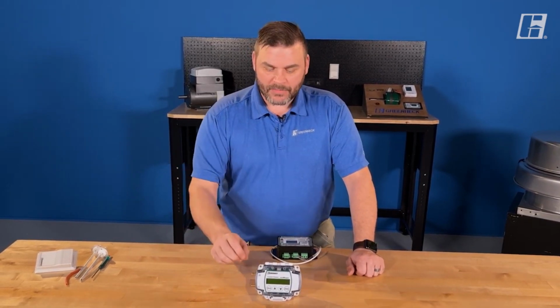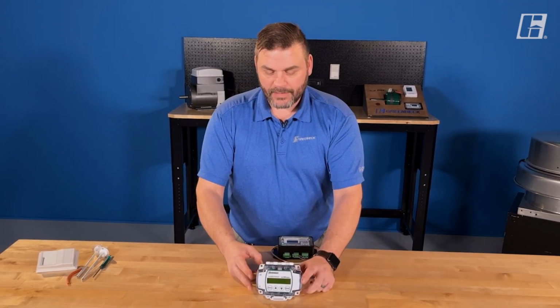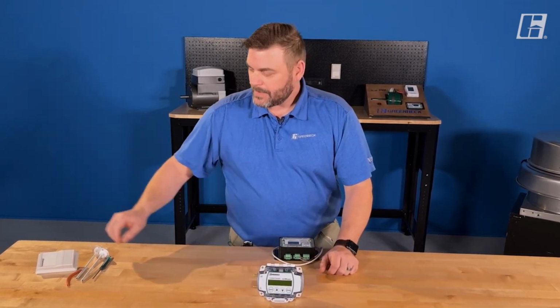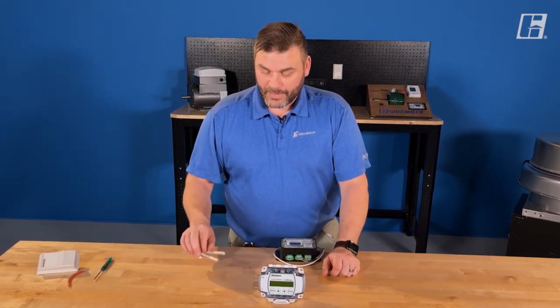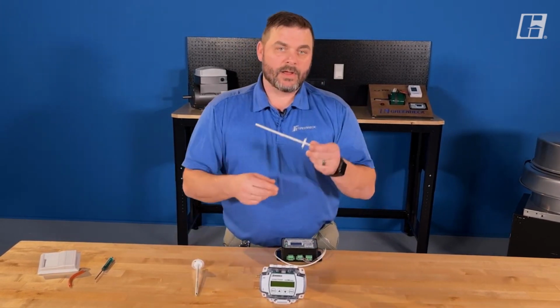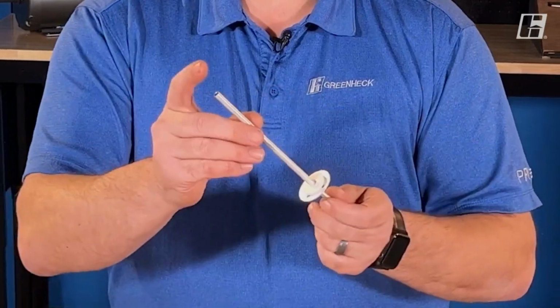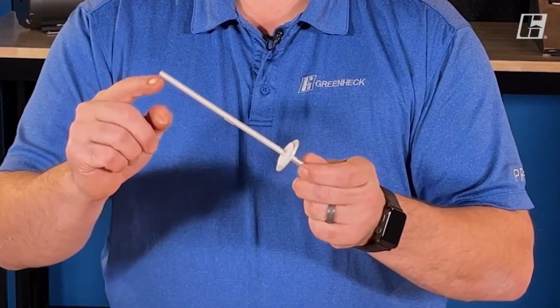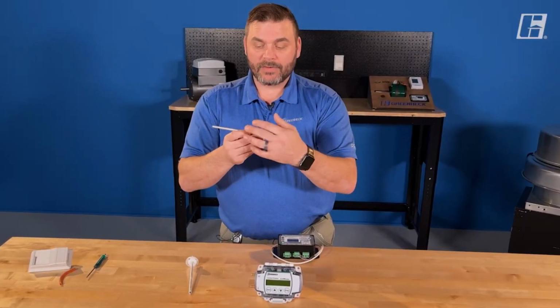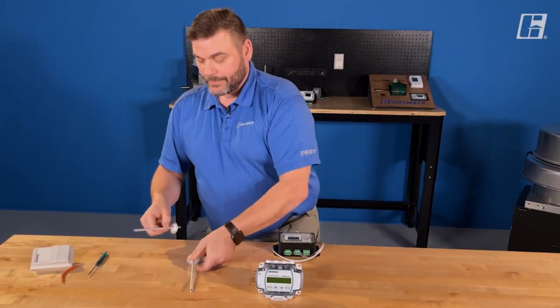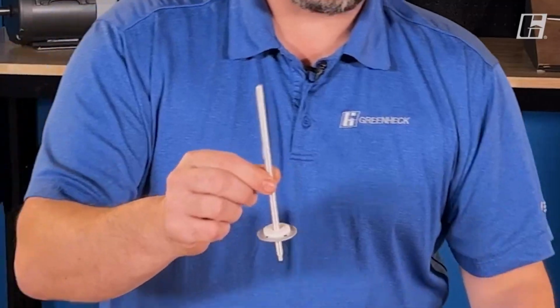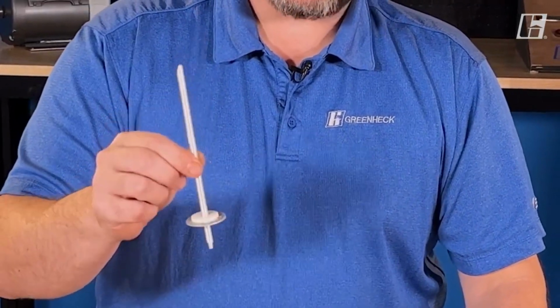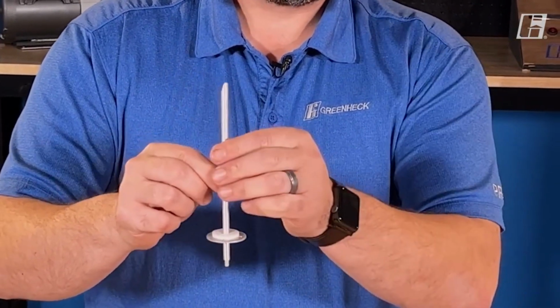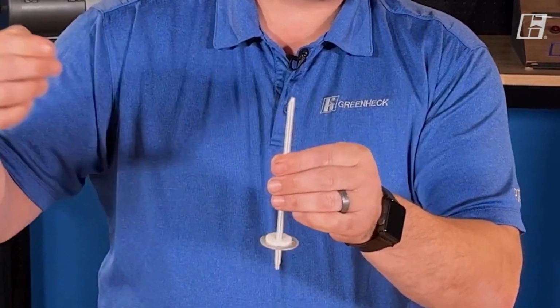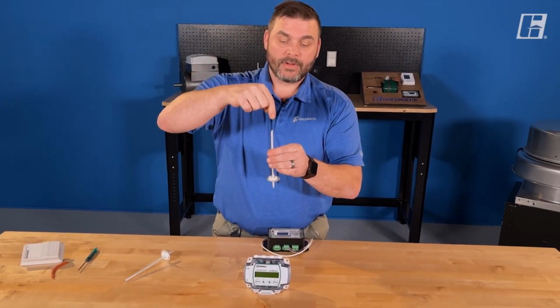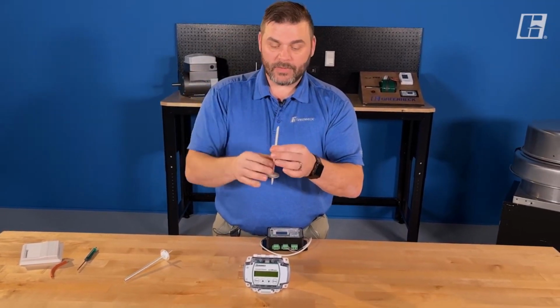Now, to monitor those pressures, I have my ports here on the device, a high and a low, and then I'll have accessories to go along with it. Here is a duct static pressure probe. You can tell it's a static pressure probe because it's got a flat cut. This could help me monitor pressure within a duct. This probe, which looks very similar, is actually a total static pressure probe, and you can tell because it has a bias cut. It's actually taking both static pressure and velocity pressure into account.